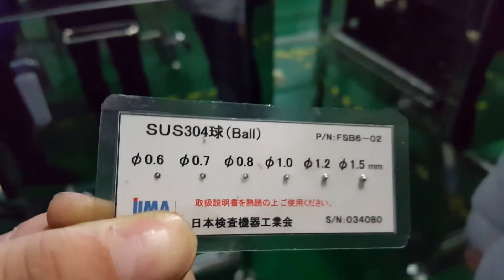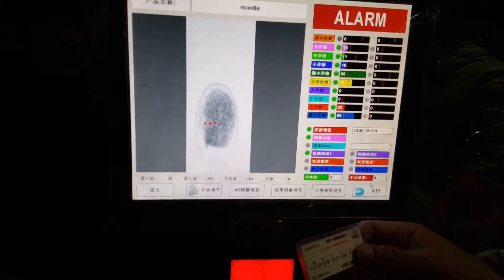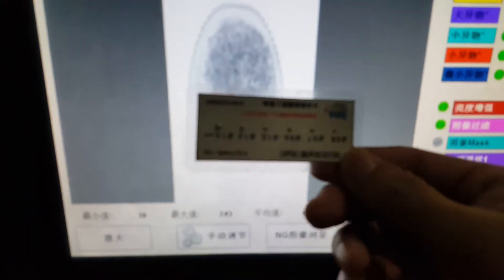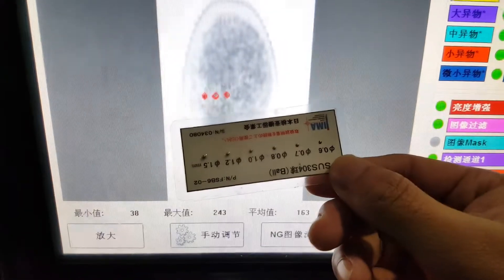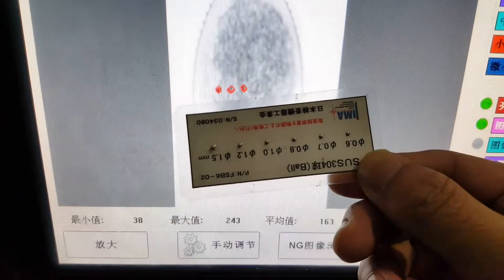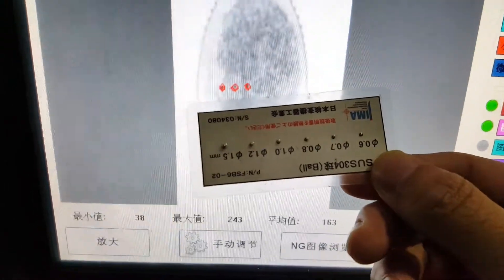Next, we put the stainless steel ball into the product. We still hear alarms, and you can see there are three red points. The best sensitivity for stainless steel is 1.0 millimeter.